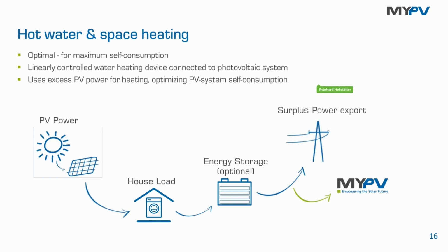All right, so where does the energy come from? It comes from the PV system. That's clear. First application is for direct electric appliances in the building, the washing machine, the dishwasher, and so on. This has priority by the laws of physics. And then priority is on the battery, if there is a battery. It's not required when you combine MyPV with IME, it's an option. So both ways are possible. If there is a battery, once again, the charging of the battery has priority before our application. But if there is no other way to use the electric power, we make use of it for heating before the energy goes back into the power grid.